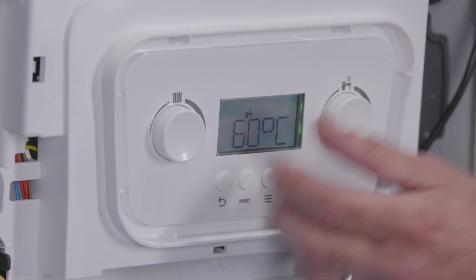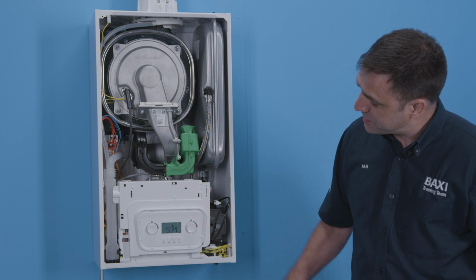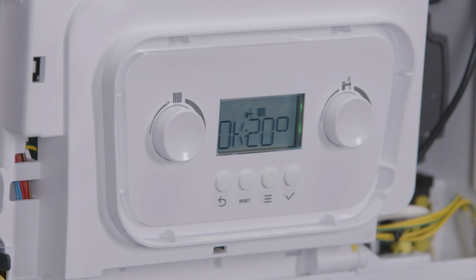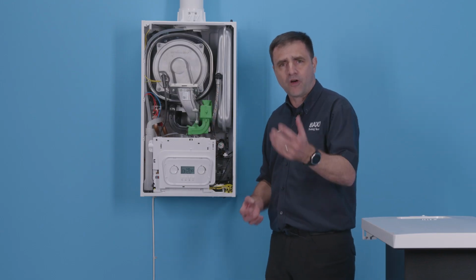So we're going to turn both of these on. You wait for the display to go back to normal. And now you can see my heating indicator is flashing. I've got a heating demand and it will run through its sequence and fire the boiler.